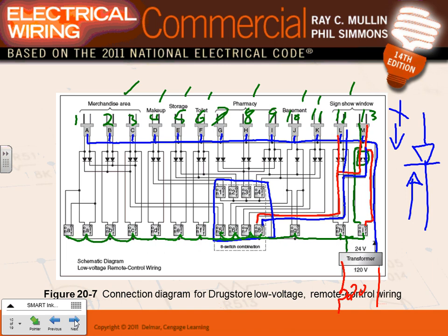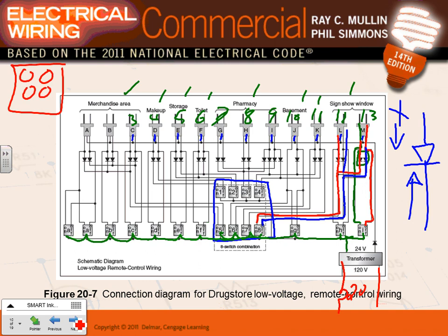The only thing that's not shown here, guys, it might be confusing to you. I want to show that a room like this has a couple of lights inside it, and I'm going to power it. So I bring a separate 20 amp circuit. Can you guys see that? And my 20 amp circuit, I bring to this side. Can you guys see it? To this side of the fuse of the relay number one, and from here, I'm going to feed these.